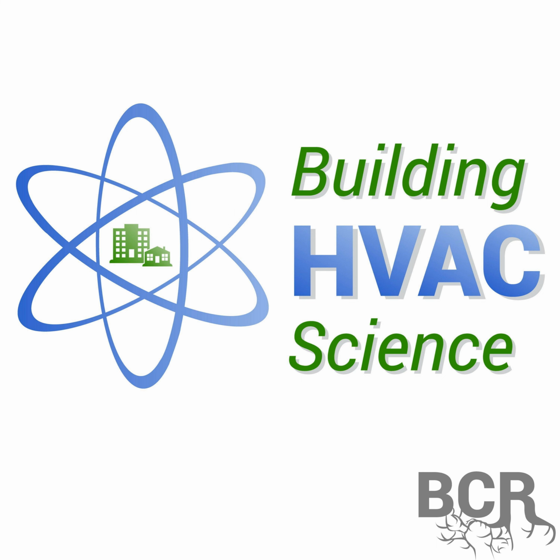Yellow, okay, something has to be modified. That could be as simple as a hot gas bypass tuning. That could be a TXV twisting. That could be replacing the metering device. That could be oversized TXVs, pump down circuitry, whatever it might be. And then it tells you in the app exactly what to do to tweak that system to enable it to run well under a blend.